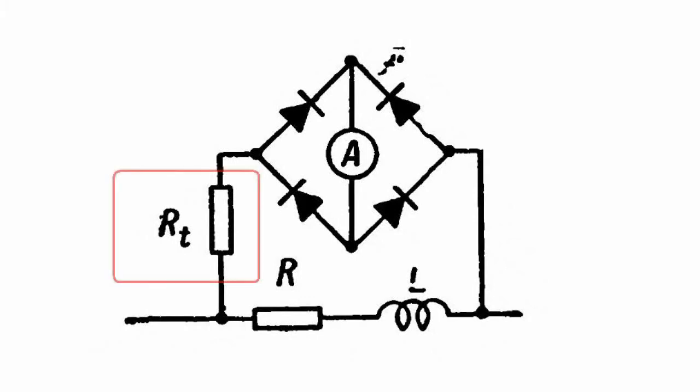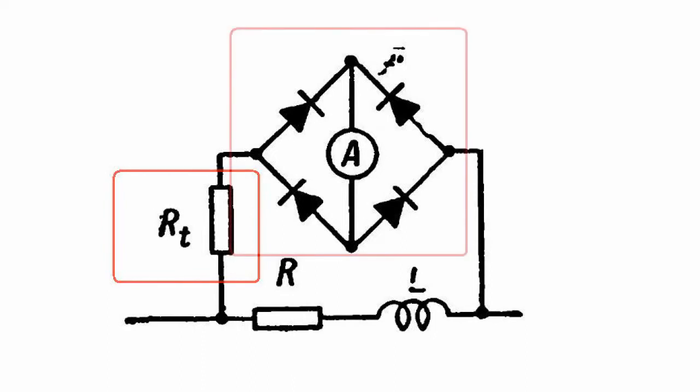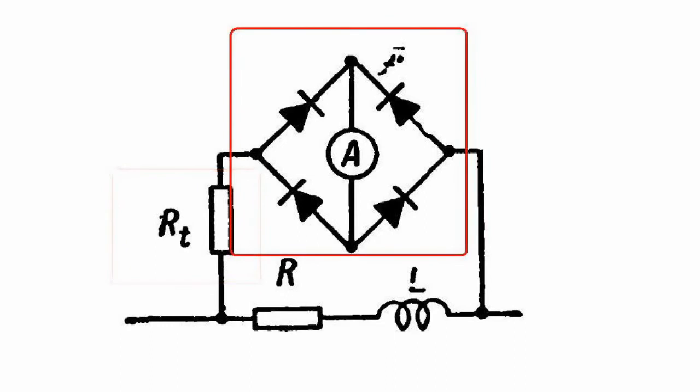Resistance RT is made of material with a high positive temperature resistance factor of about 0.02. It serves to compensate for the negative temperature resistance factor of the rectifiers.